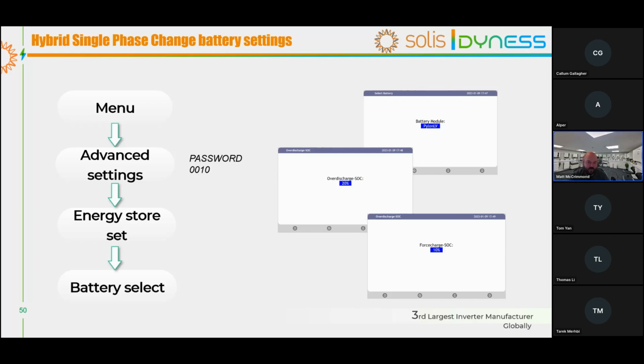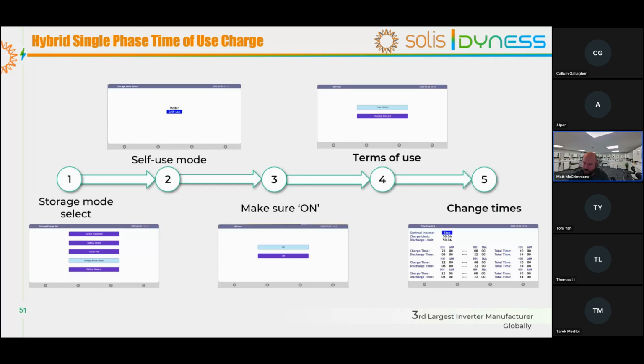So typically customers will increase the battery capacity of their battery bank, but then use less of it in normal operation, but leave some in reserve, so that if there ever was a failure of the grid, then they would have power available. Hopefully I've explained that properly. I feel like I kind of waffled a bit, but hopefully that was okay.